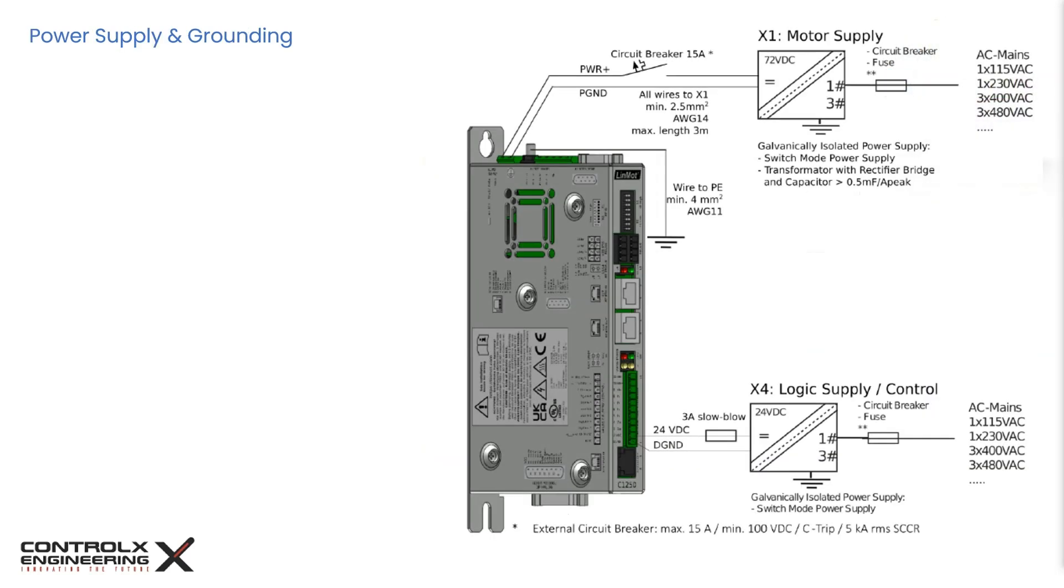This page shows the power supply and grounding connections, as well as the recommended wire sizes. The nominal supply voltage for the motor supply is 72V DC, and the possible range for this model is from 24V up to 85V DC. The power source must be able to supply at least 6.5A.